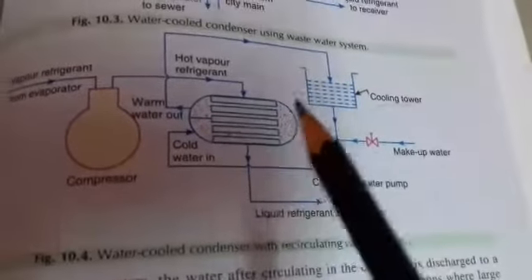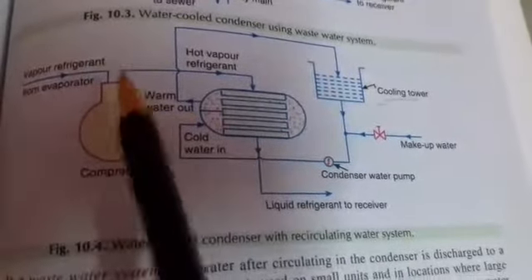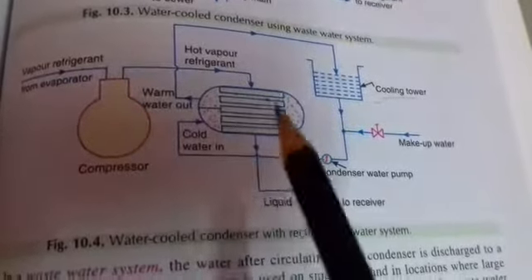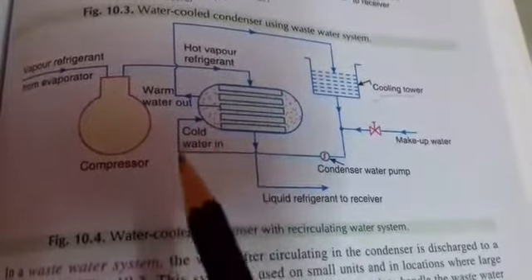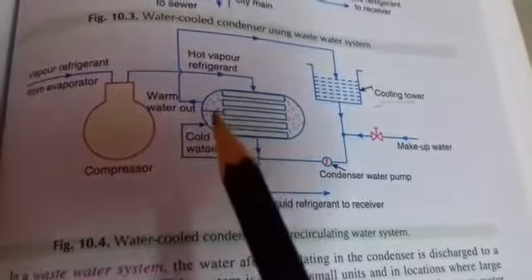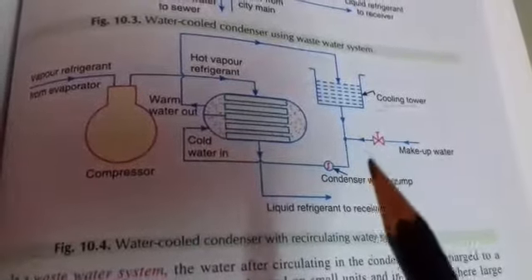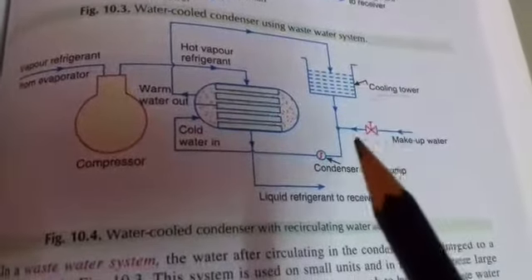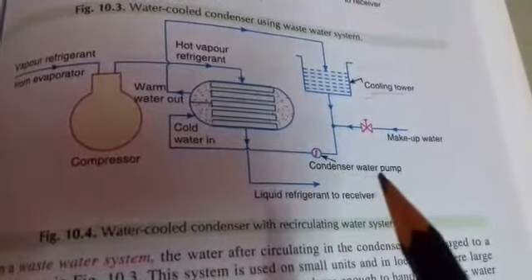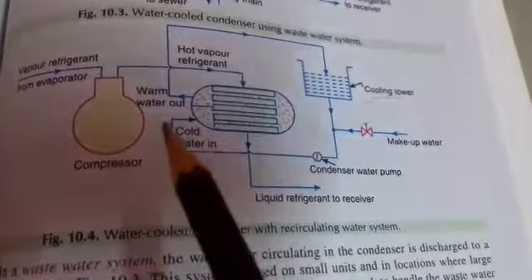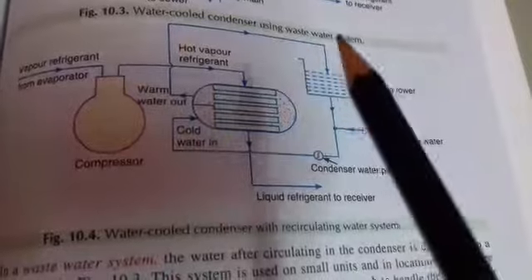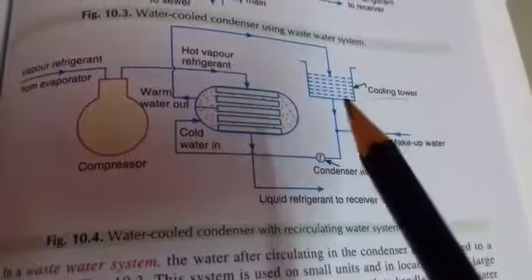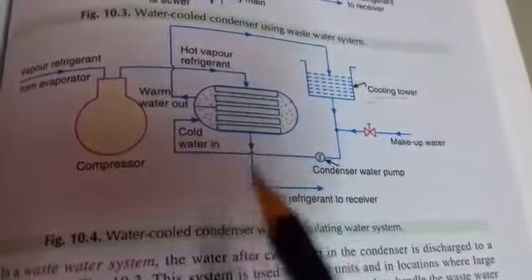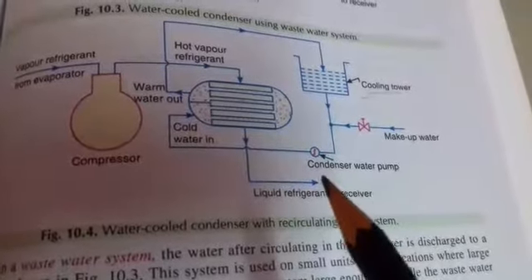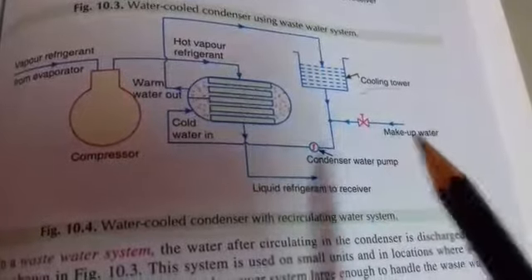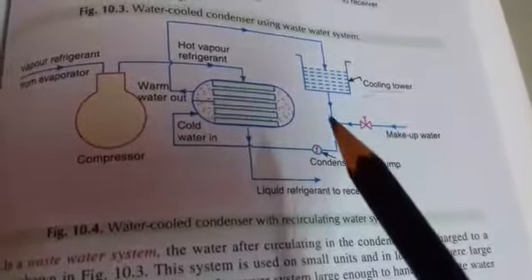Another one, that is the water cooled condenser with recirculating water, means same water is used repeatedly. Here compressor, then again refrigerant goes to the condenser. Now in condenser, the cold water that is coming from the cooling tower, then condensing pump is there, that water comes into the condenser, and from out it goes directly to the cooling tower. Here the water is being cooled, and then it is going back to the condenser through your condenser water pump. One makeup water device is also there, because of the evaporation, the water evaporates, so makeup water is also there.